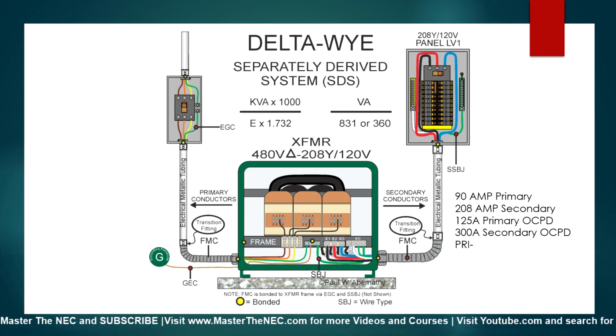So in our case, going back to the graphic, this one was only a 208 amp output, but using the 125%, we ended up sizing this at 300 amperes. Now, in the real world, that's probably not going to work, because this is really not the protection for the secondary, since it was not higher than 125%. I would really only size this based on my calculated load.